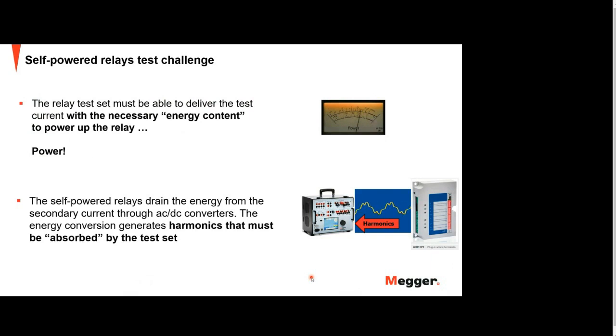Self-powered relays drain the energy from the secondary current through the AC-DC converters. So the energy conversion generates harmonics that must be absorbed by the test set. So when the relay test set generates current, there is a lot of distortion of the sine wave, and this could cause wrong readings in the protections. So that's a big problem, because you set, for example, 1 amp to run from the relay test set, but actually the relay is measuring 0.7 amps. And you will get a wrong result, actually.